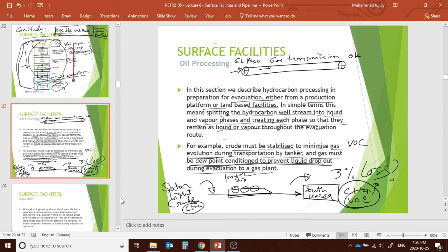They had a problem with corrosion, and the pipeline integrity had issues. Why is that? There are several reasons, but one of them was that the natural gas had condensates. What are gas condensates? Just like crude oil has dissolved VOCs, like methane, ethane, propane, butane, natural gas has some oil condensate, small droplets of oil. If the temperature goes low, these oil condensates get condensed, and it creates a dew point. If the gas is below this dew point, the condensate appears. Since the pipeline is at very high pressure, usually around 700 PSIG, this liquid condensate can hit the natural gas pipeline and destroy it.